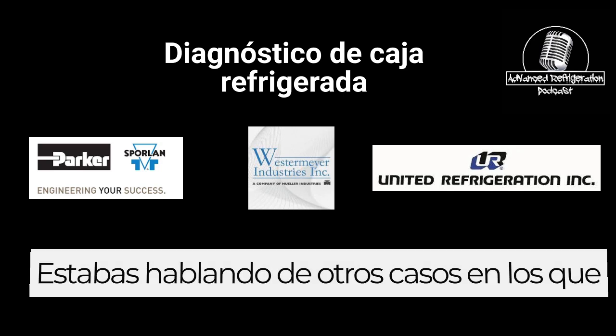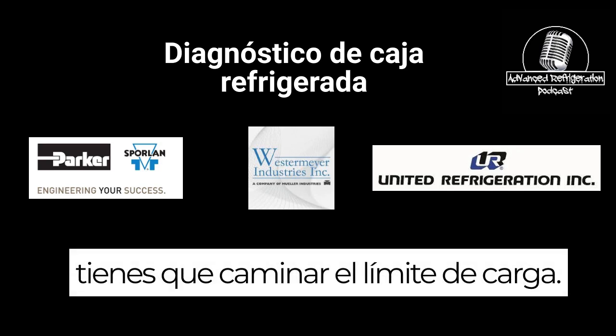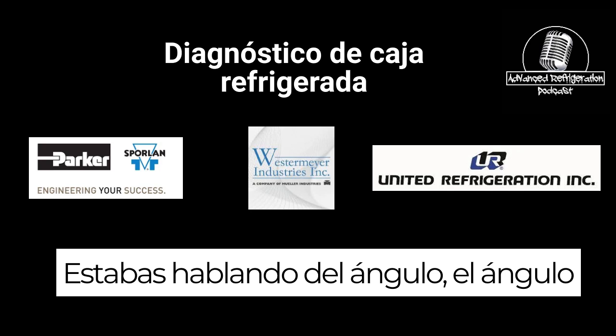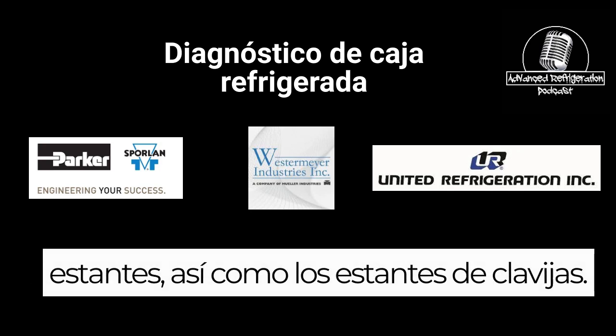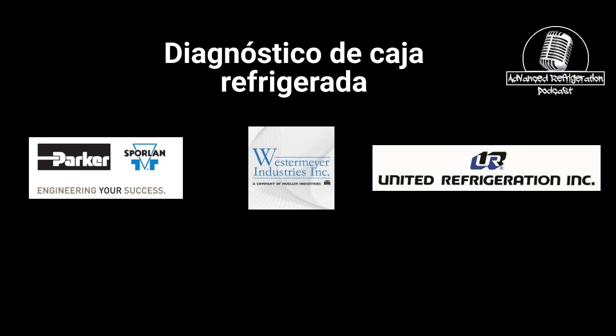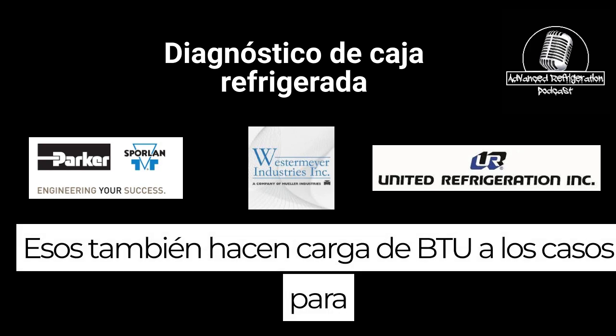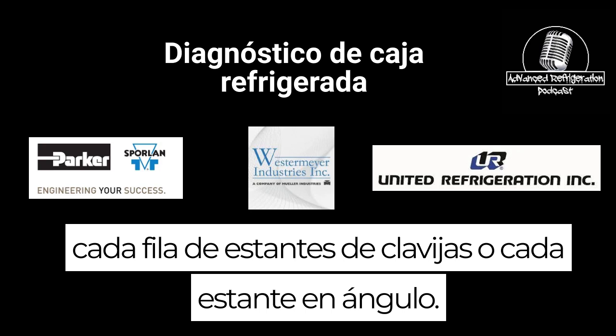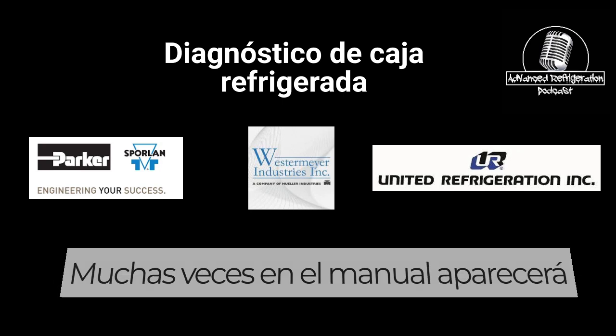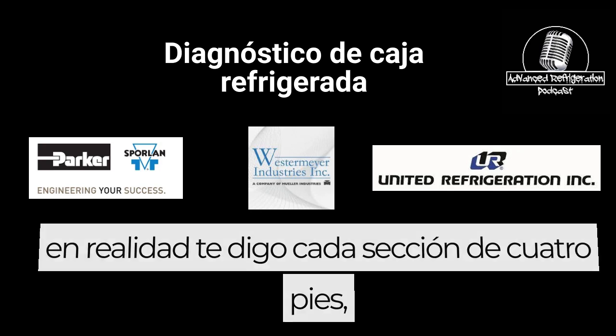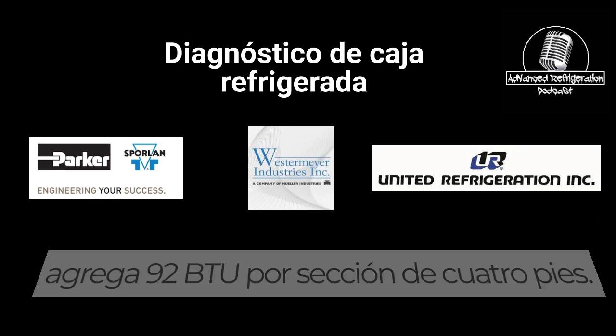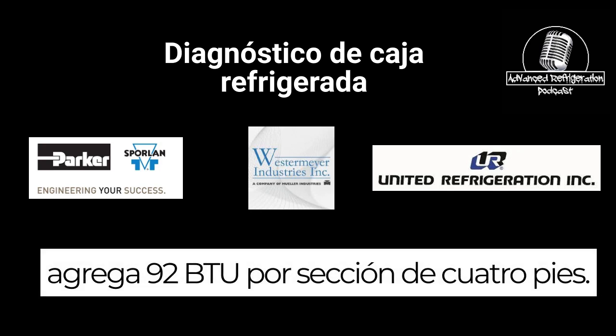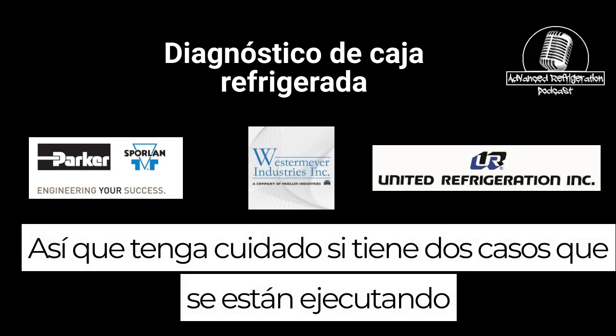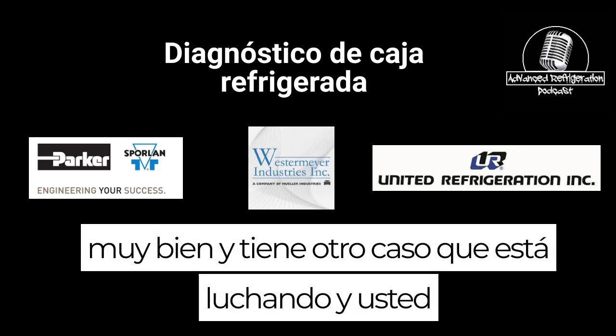You were talking about some other cases where you have to watch the load limit. You were talking about the angled shelves as well as the peg shelves. Those also do add BTU load to the cases, for every row of peg shelf or every angled shelf. A lot of times in the manual, it'll actually tell you every 4 foot section adds 92 BTUs per 4 foot section.